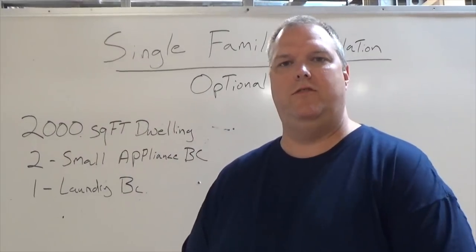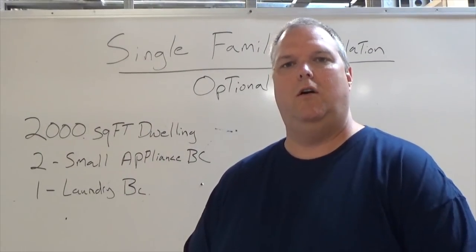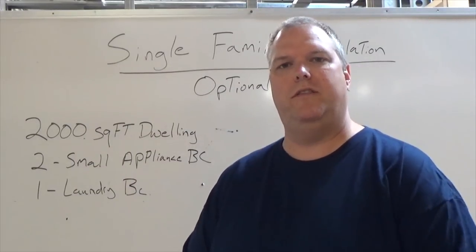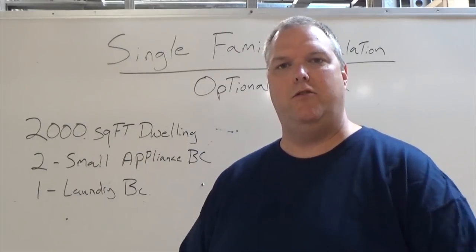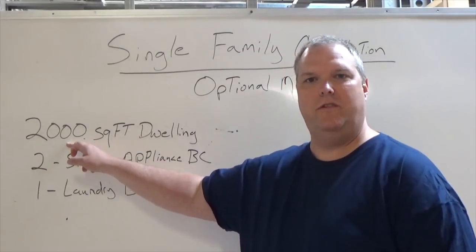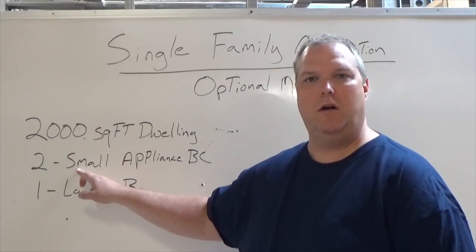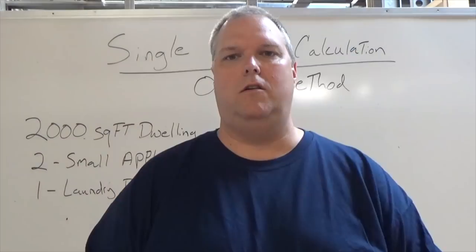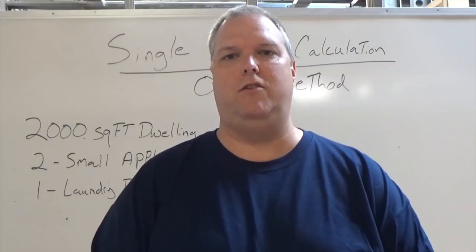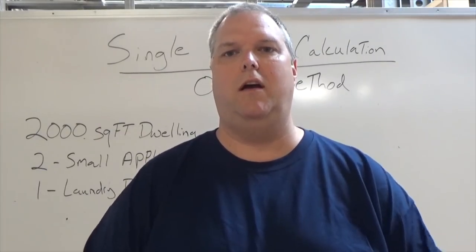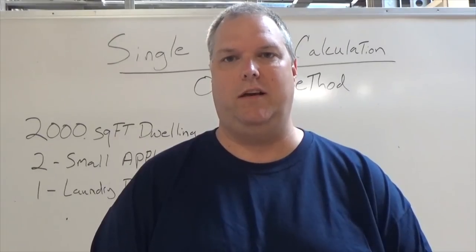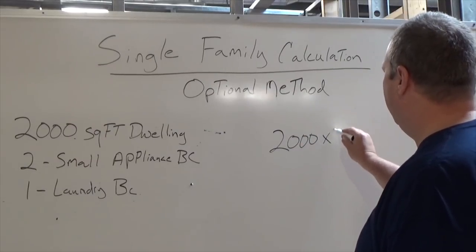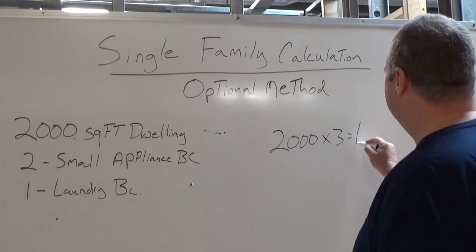The first step is the same as we would use in the standard method. The three most important things we have to know — whether doing standard or optional — are: the total square footage of the dwelling, how many small appliance branch circuits we're installing, and how many laundry circuits we're installing. Using the multiplier from NEC table 220.12, we multiply the single-family dwelling square footage — 2,000 — by three, which gives us 6,000 VA.